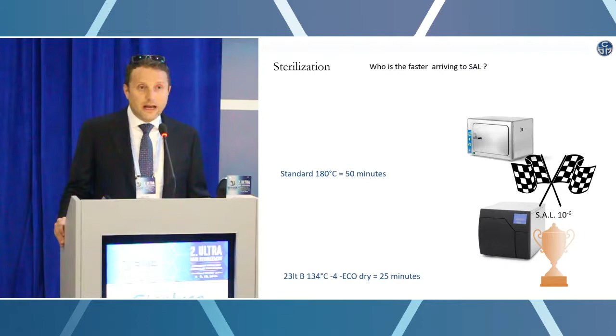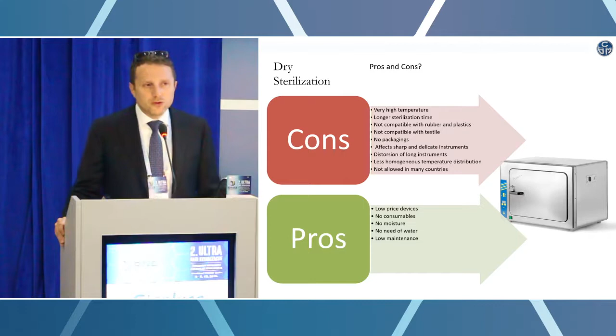it works at very high temperature, so if we have very sensitive material, we cannot process it in a dry sterilizer. Also, it is quite difficult to use packaging inside a dry sterilizer. There are some pouches, but they are, let's say, very rare and very difficult to find. For all the other pouches, people invent all kinds of methods. They moisten the pouches, they moisten the gauze, and they put them inside a dry sterilizer. But this is absolutely not the correct way to work. So when you are using a dry heat sterilizer, practically you cannot use packaging material.